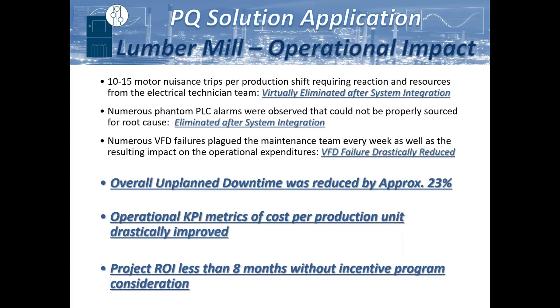Once we put in these systems and we're able to optimize that voltage level and keep a steady state condition, all of their nuisance tripping basically went away. The phantom PLC alarms that they had never associated with power quality just went away. And their VFD repair failures went down dramatically. Now, obviously, you're still going to have some pre-existing conditions, but that's why we like to look at it over time, because you can see that after those pre-existing conditions have worked out, all of a sudden it just precipitously falls each year. And then they reduced their unplanned downtime by 23%.